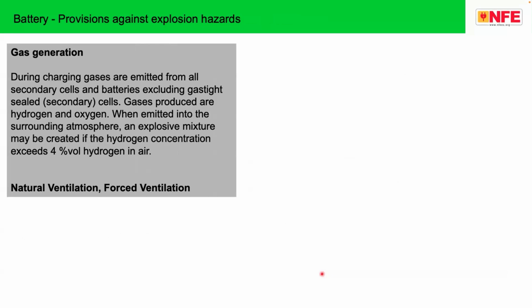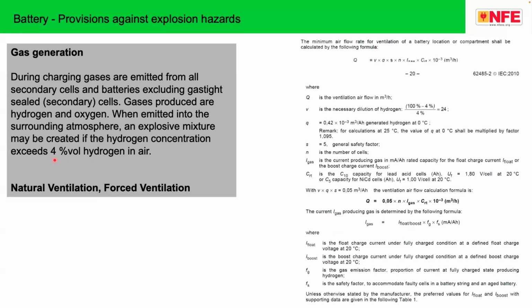Battery in the UPS, another important subject. During charging of the battery, gases are emitted from all secondary cells. Gases produced are mainly hydrogen and oxygen. If the concentration of the gas, especially hydrogen, is more than 4% of the volume of the air, then there is a chance of explosion. Now, in this particular location, you need ventilation, which can be provided either by natural means or by forced ventilation.